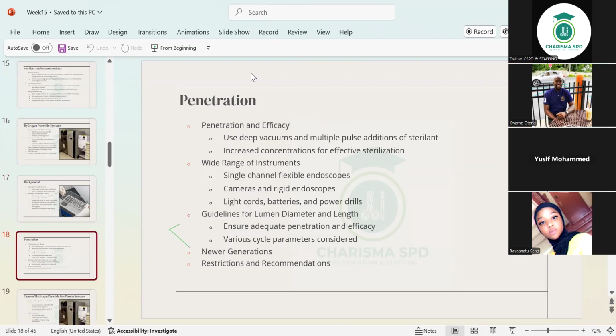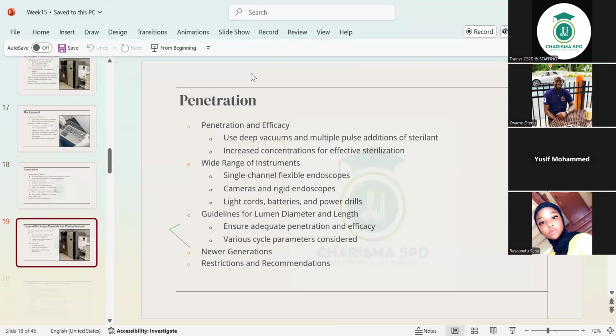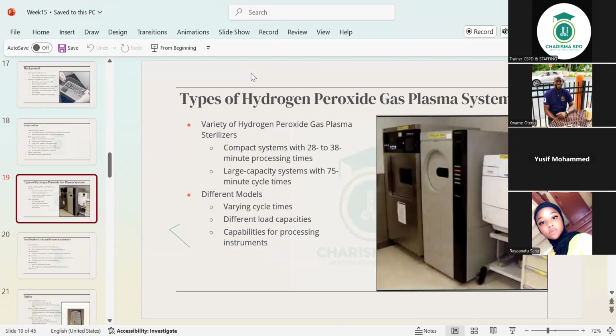With that, we use the low temperature to sterilize. There are guidelines for the lumens, as I said already. All right. Various cycle parameters are considered, and there are newer generations, but it has its own restrictions and recommendations. Like the one that we use at my facility, we make sure the instruments are well dried before they go in there. Even though the system will be removing water from the instruments, we make sure they are super dry, well dried. The camera should be well dried before going in there.